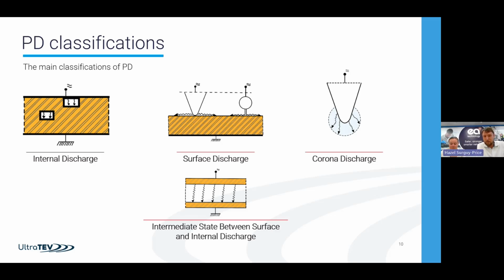Luckily, about 70 to 80% of the activity is surface activity. This is stuff that's occurring on the surface of the insulation. This might be on the bushing, etc., tracking down the outside, and is the carbonisation we saw visibly on the last picture. The stress has got to build up for some reason on the surface. That could be from a sharp point, an earth point that's local to it, or a point of other potential, or it could be from impurities, high humidity, etc. Once that's started, there's a weak point and it'll continue.